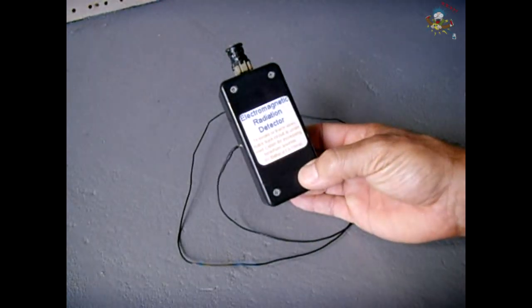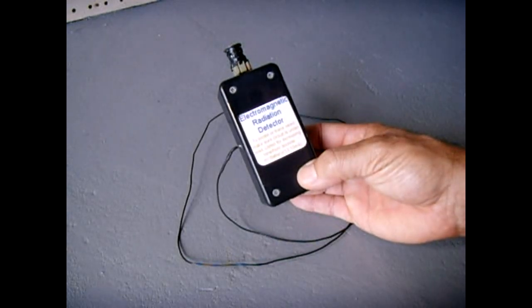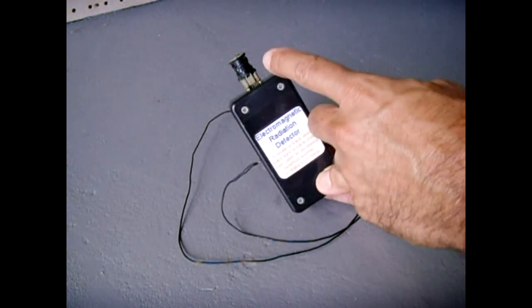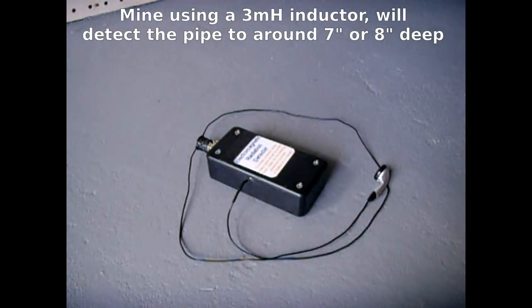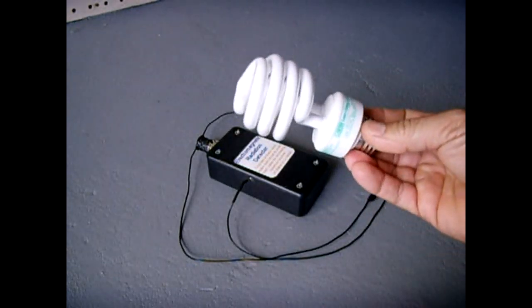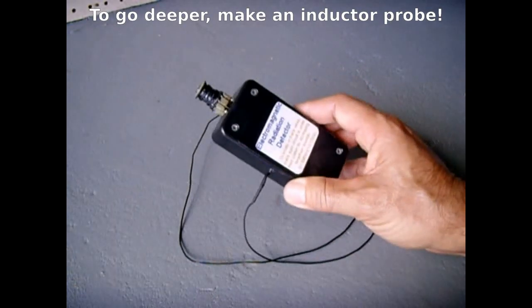If you have a PVC pipe outside your home that's supplying power to an electrical receptacle or exterior lighting and you're trying to locate the path of that pipe and it's buried in the ground, as long as it's not buried too deeply and you hold this sensor fairly close to the soil and you have a compact fluorescent light screwed into the light fixture or hooked up to a drop light which is plugged into the receptacle that you want to trace, you will be able to pinpoint the location of that buried pipe.